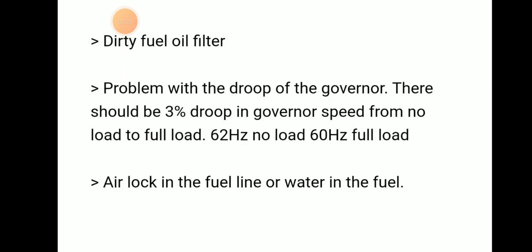Another reason is a problem with the governor droop. There should be at least 3% droop in the governor speed from no load to full load. If it is smaller than that, there will be a problem with the governor droop — for example, 62 Hz at no load and 60 Hz at full load.